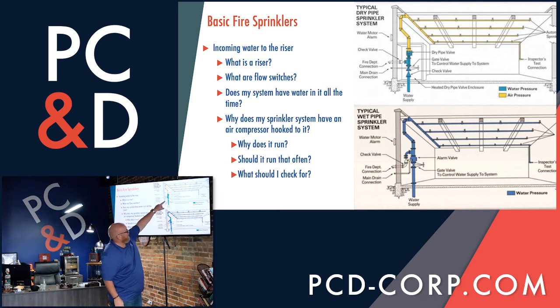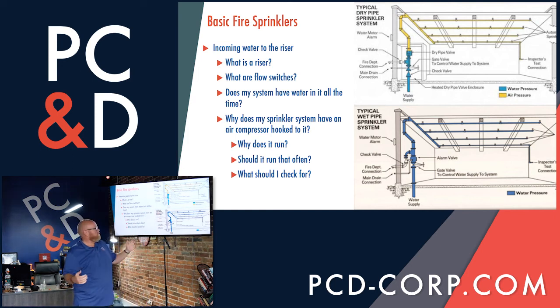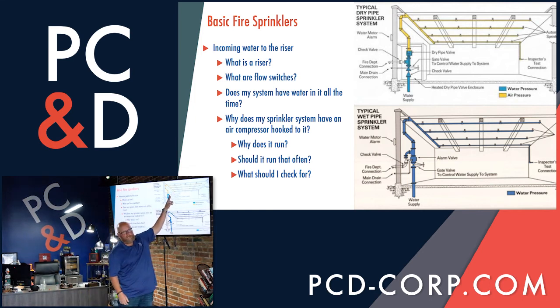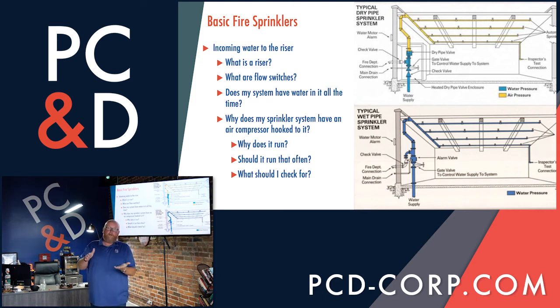So you have right here what's called your dry pipe valve, or also sometimes known as your flapper valve, in your riser. The way a dry system works, your air compressor always keeps the yellow pipe, shown in this diagram, full of air, okay? The purpose and the point of the air is to hold back what we call the flapper valve or the riser valve. You've got air on top, you've got water on the bottom. There is a fancy engineering term that you can calculate for every square inch of that valve. You have to have a certain PSI of air pressure to hold back water pressure.